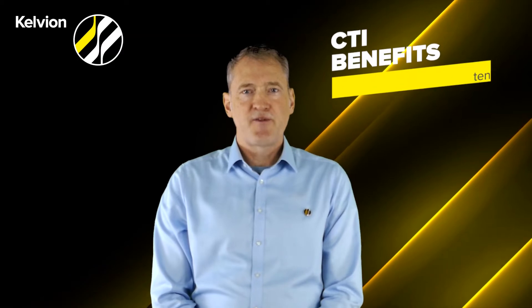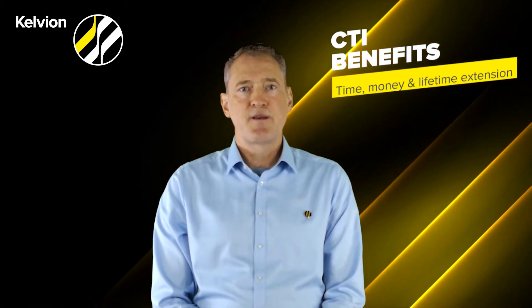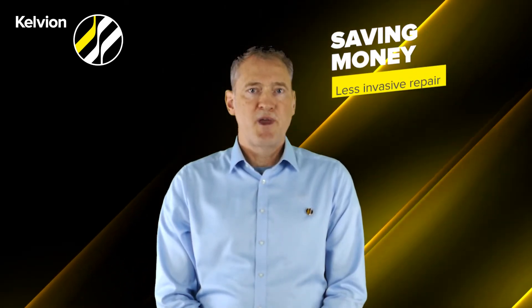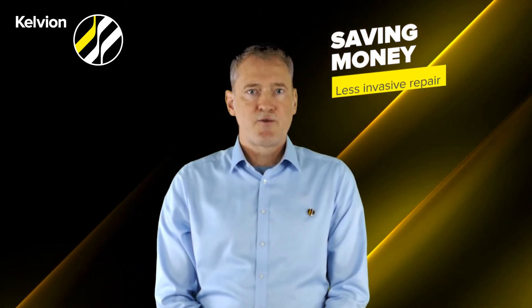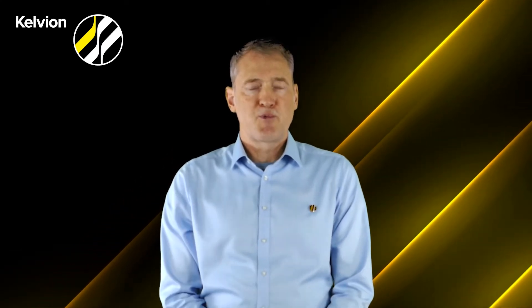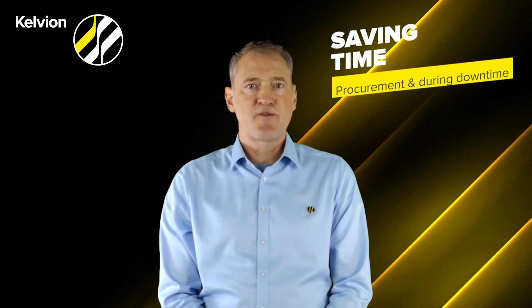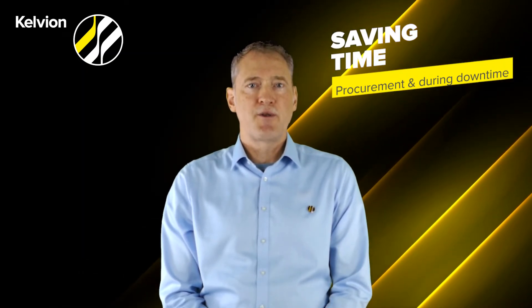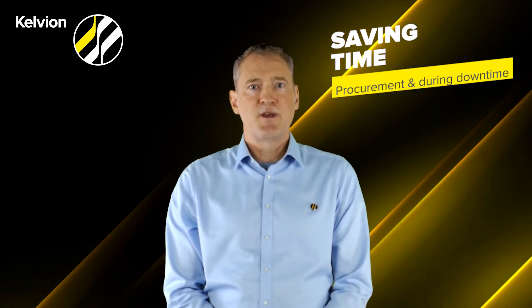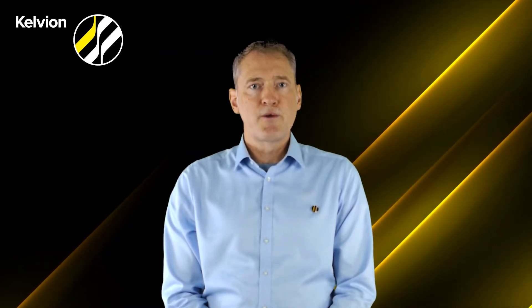The benefits of these solutions are saving time, saving money, and extending the lifetime of the heat exchanger, as the entire repair method is less invasive. We will save around 30 to 50% compared to a conventional repair. The procurement time is less as we just have to order the shields or the liners, and the downtime will be reduced as we have less interventions and less work, since we do not have to remove old equipment.